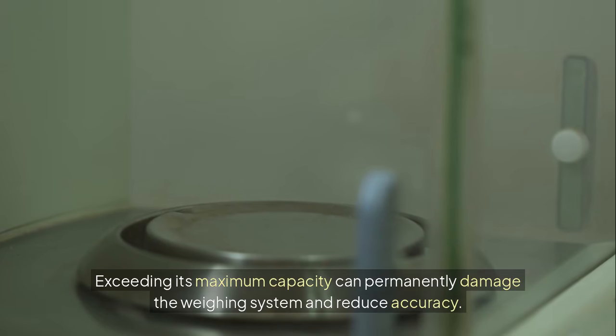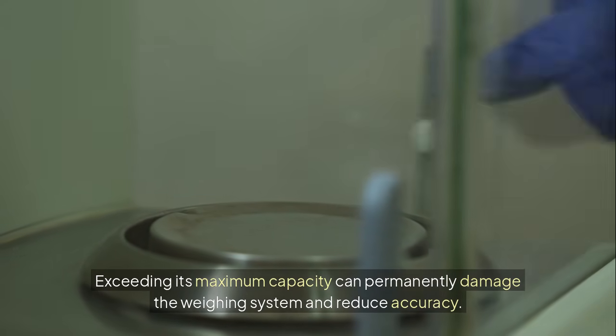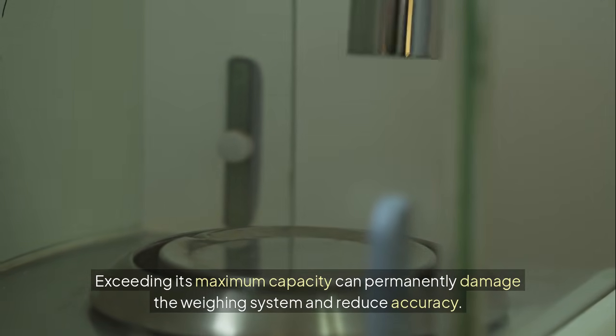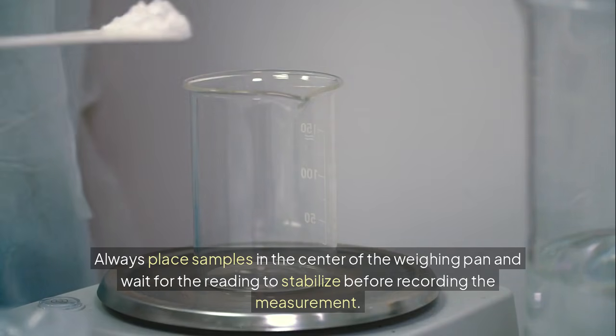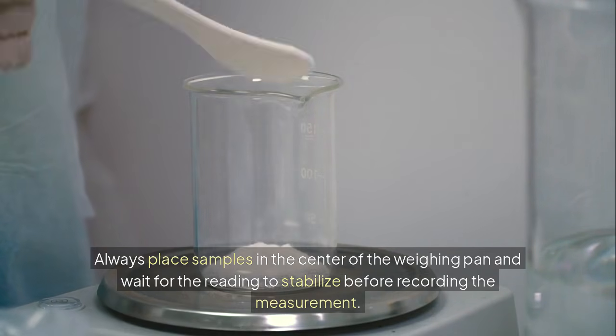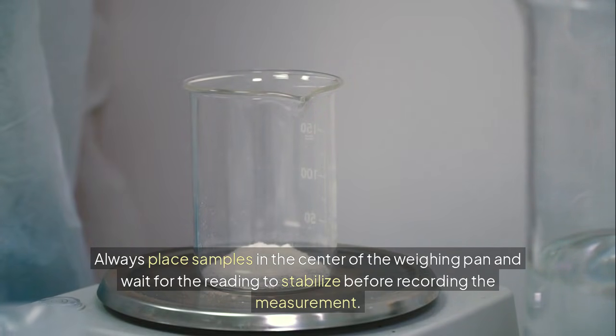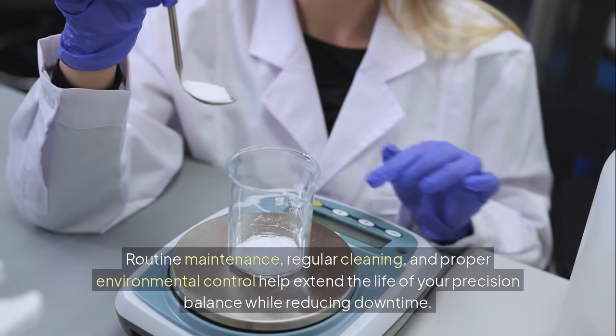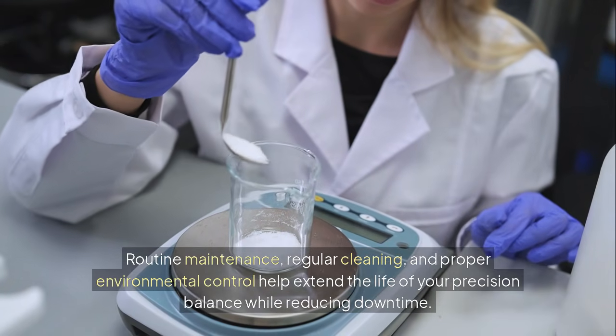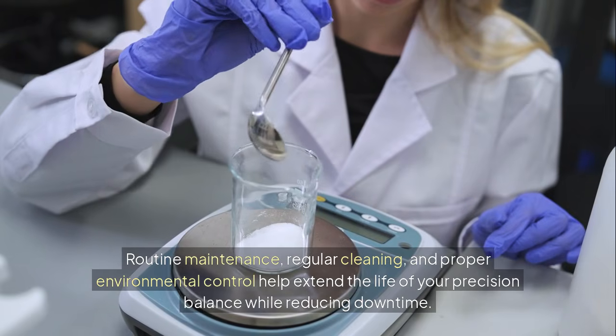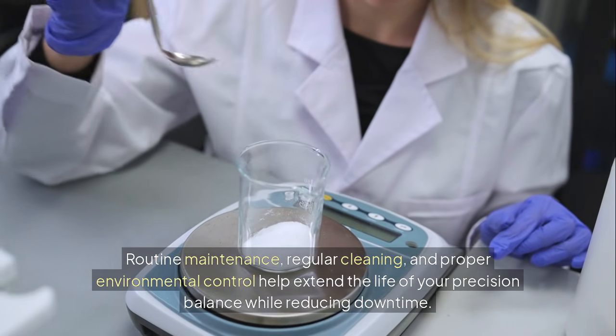Never overload your precision balance. Exceeding its maximum capacity can permanently damage the weighing system and reduce accuracy. Always place samples in the center of the weighing pan and wait for the reading to stabilize before recording the measurement. Routine maintenance, regular cleaning, and proper environmental control help extend the life of your precision balance while reducing downtime.